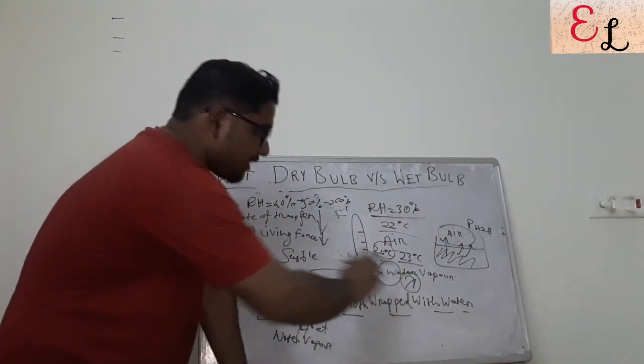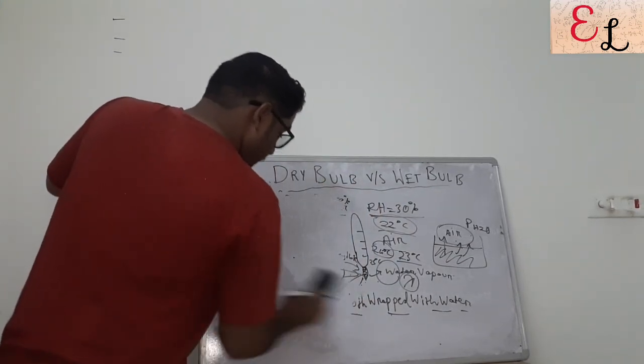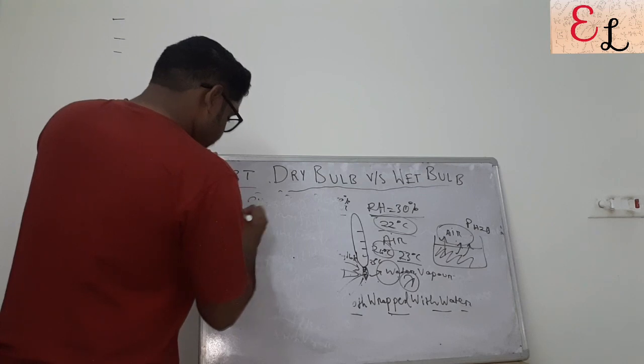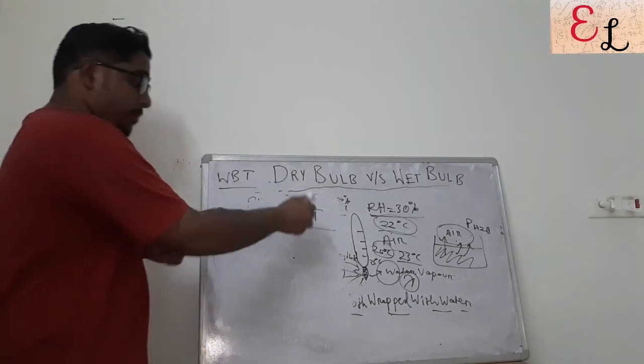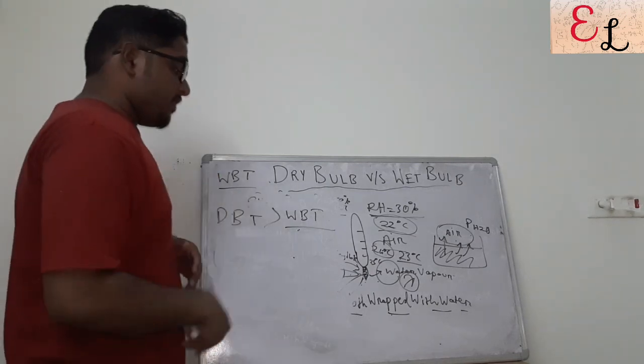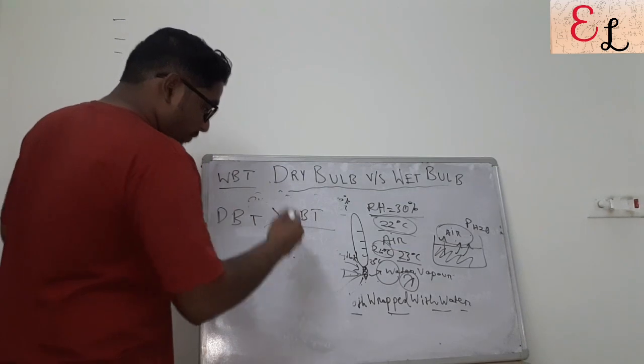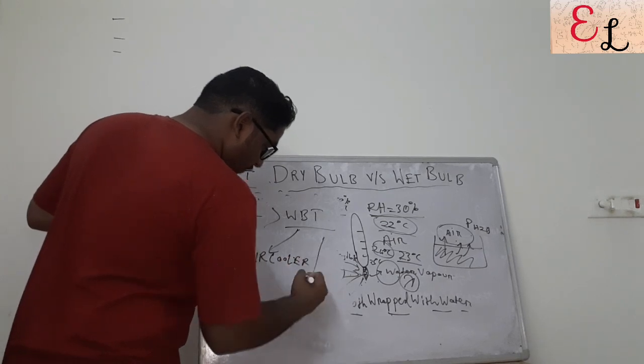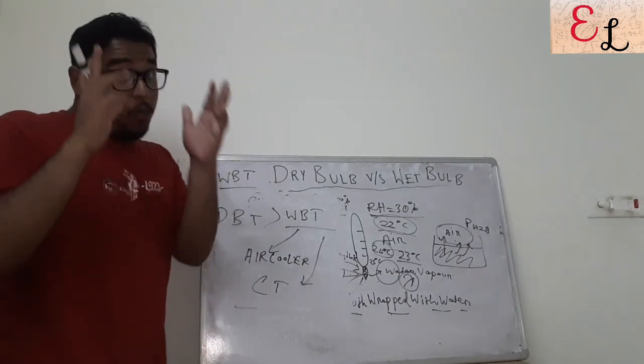At steady state, when the sensible heat given by air equals the latent heat given by the wet bulb to evaporate water, the temperature no longer changes — that temperature is the WBT, or wet bulb temperature. That temperature will be around 22°C, where the rate of heat transfer from air equals the rate of evaporative heat loss. Therefore, dry bulb temperature is always greater than wet bulb temperature. This wet bulb temperature is the driving force — once reached, no further decrease in temperature occurs.